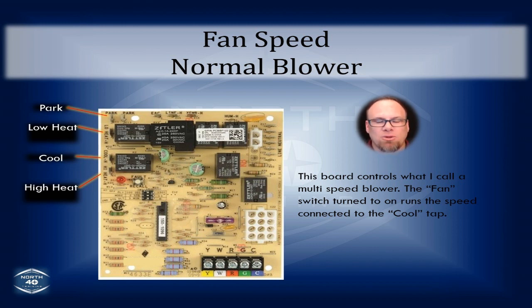Now, I told you also that one of the things that I like to do is check all the fan speeds really before I begin my setup. Checking all the fan speeds on a multi-speed blower with a board such as the one that we're looking at right now is very simple. The cool terminal on there is what's directly connected to the fan on switch on the thermostat. So if I connected the fan on switch, or I jumped out the R and the G on the board, it would turn on the speed that's on that cool terminal.